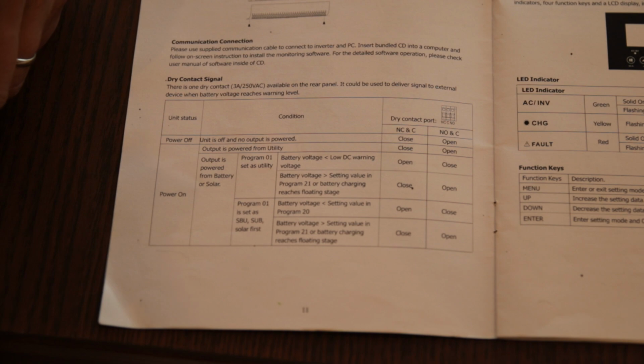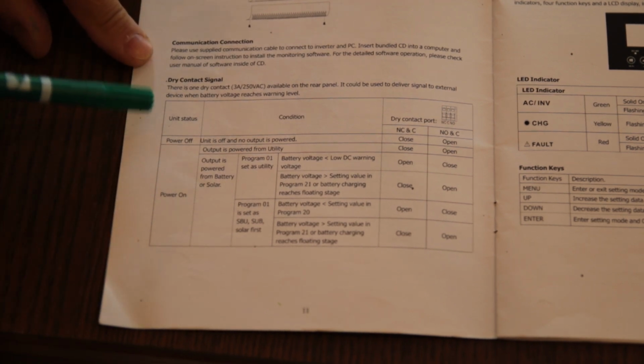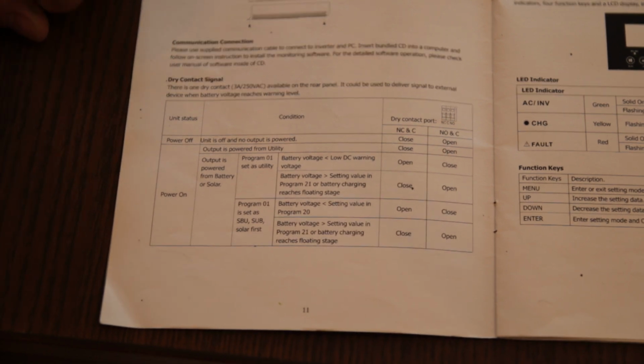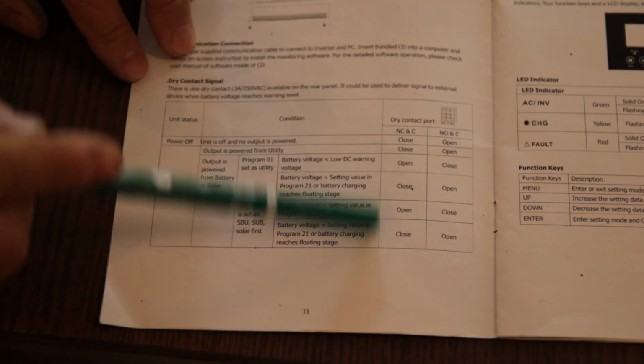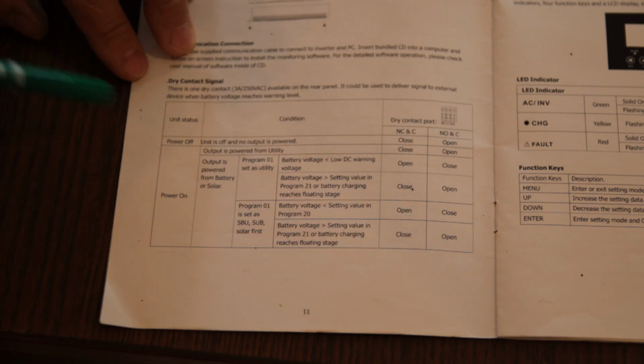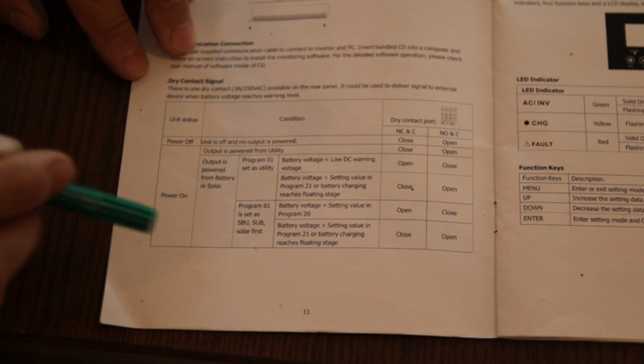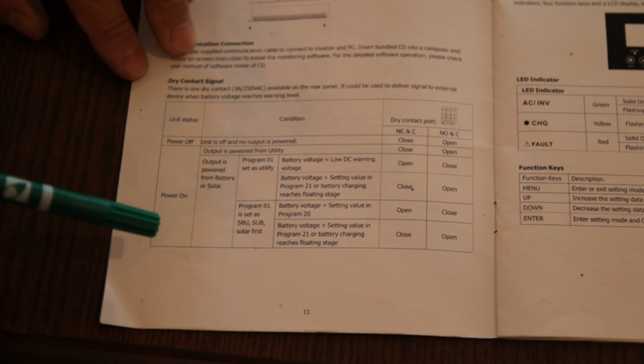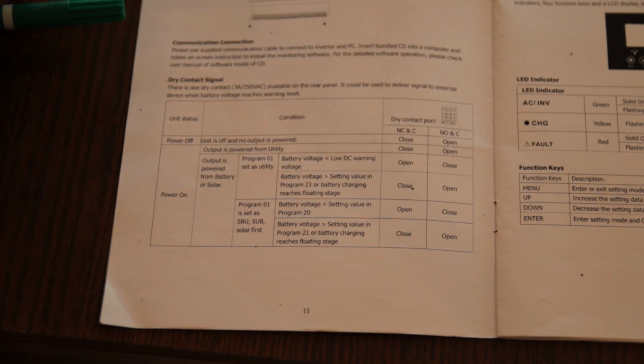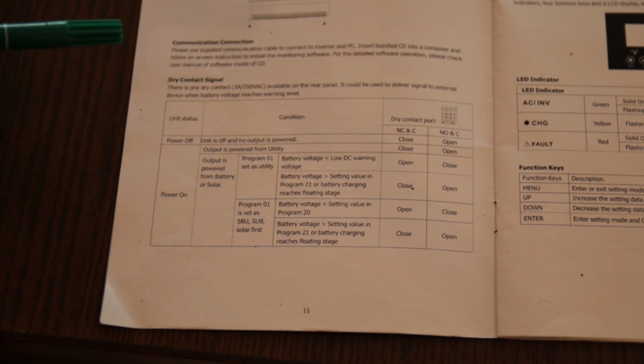When you're using the dry contact of an all-in-one inverter, then you have to study this table here. It's about the dry contact signal. You will find this in the manual which is provided with your inverter. And here you can then see the state of the relay of the dry contact depending on the modes. And when you study this carefully, you will come to the conclusion that actually only the solar first mode would behave similarly to a sort of on-grid, off-grid situational contact. Still, this is not covering 100% of cases, because this would only work when the inverter is in a normal operating state.